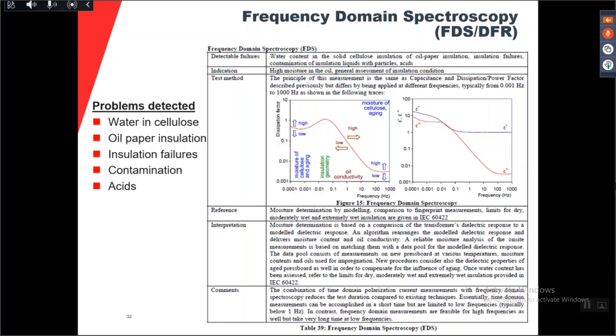Do you remember in the beginning, I said you can do the FDS, but you can also do the PDC and the RVM. The problems detected are the exact same thing. So there is no use in describing the different tests in another way, because I prefer to do the FDS, and I will come back to why at a later stage. The test method I will also show, but the principle of the measurement is exactly the same as the capacitance and dissipation power factor measurement, but you do it at different frequencies.